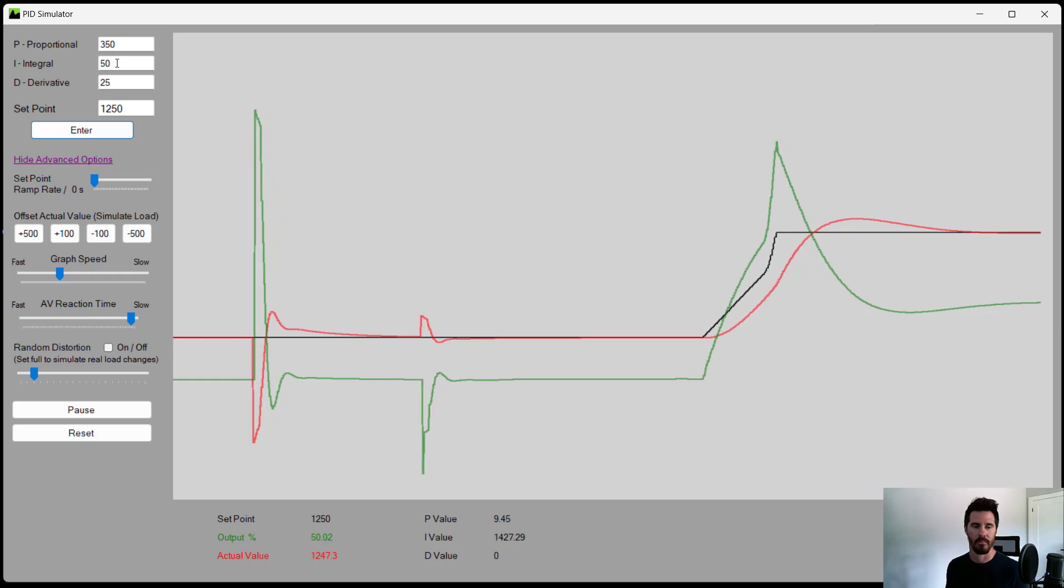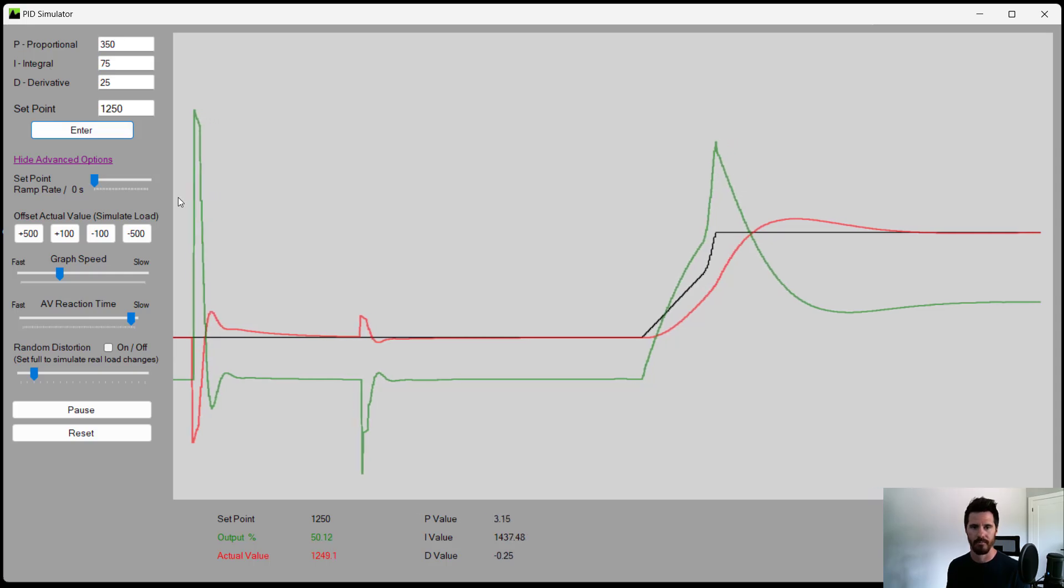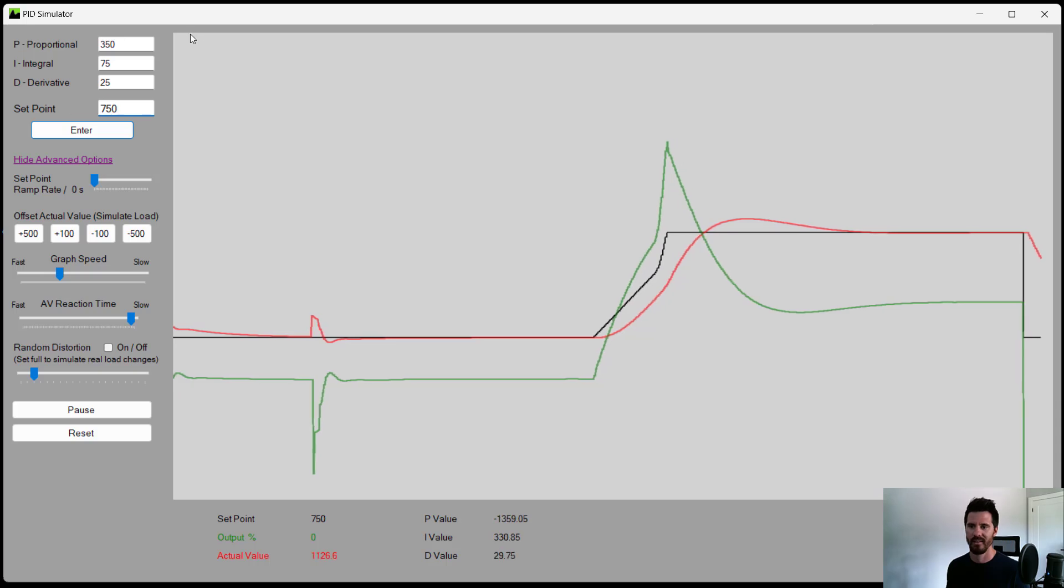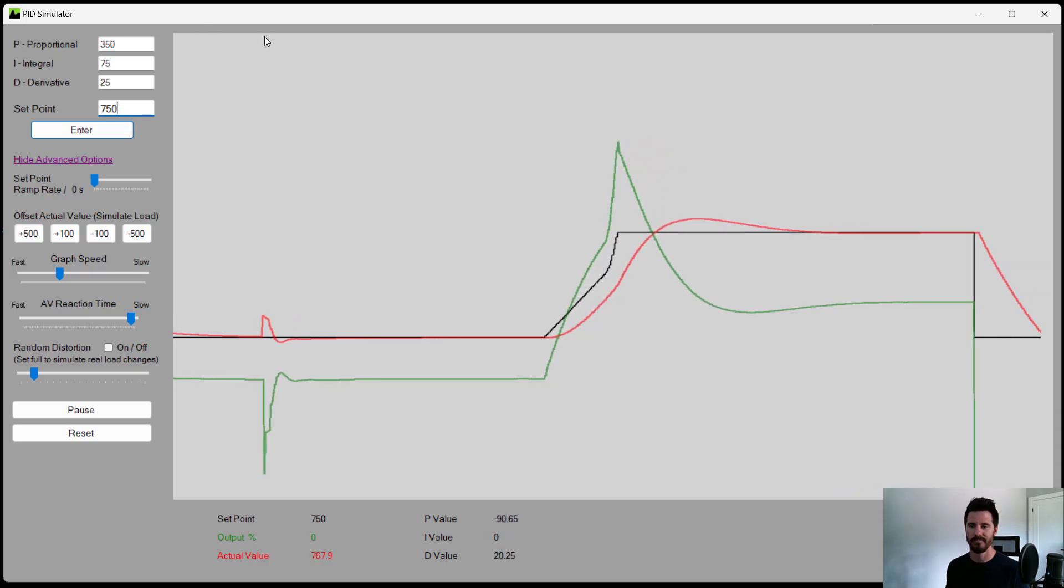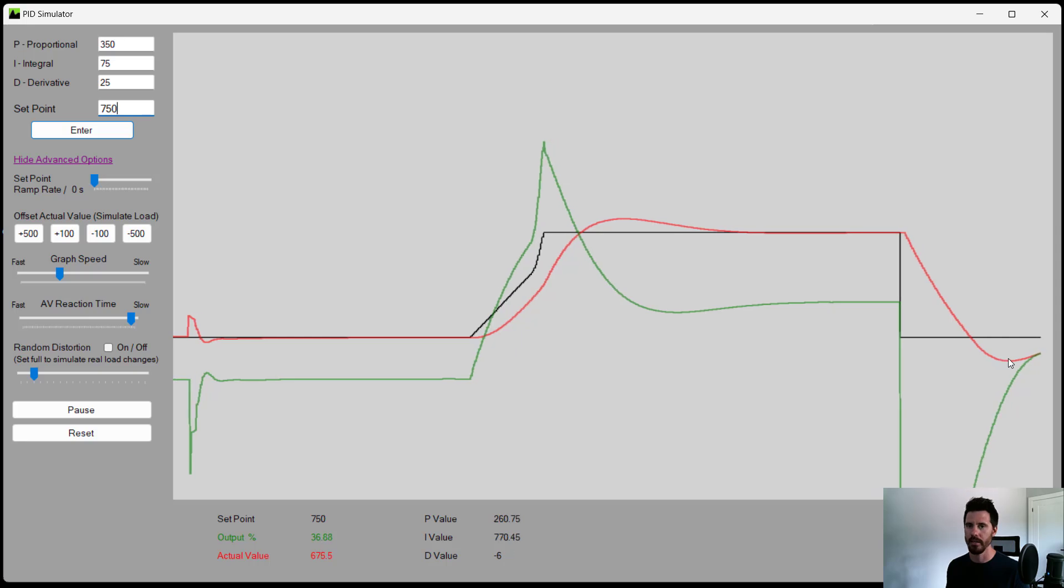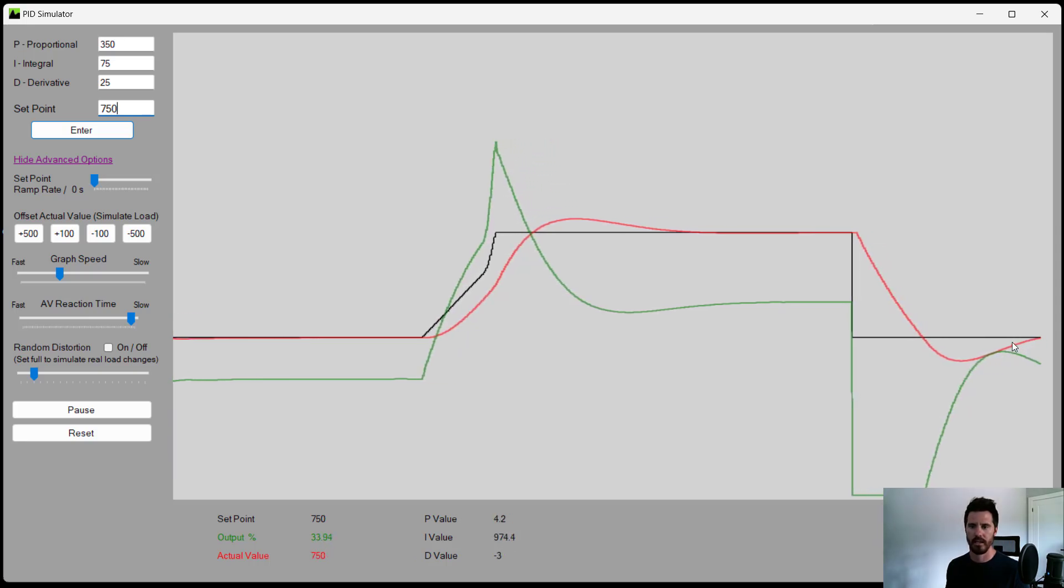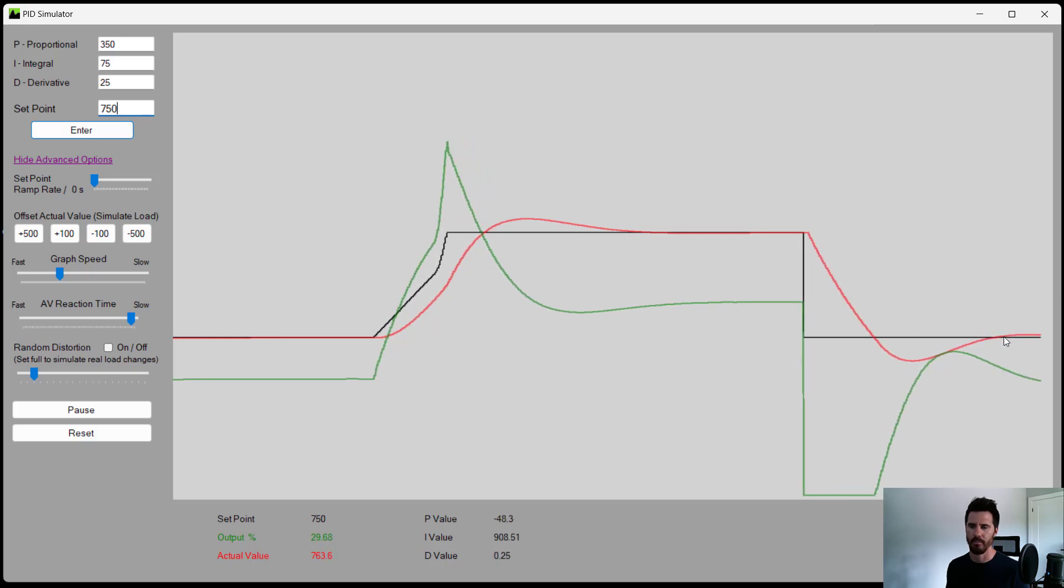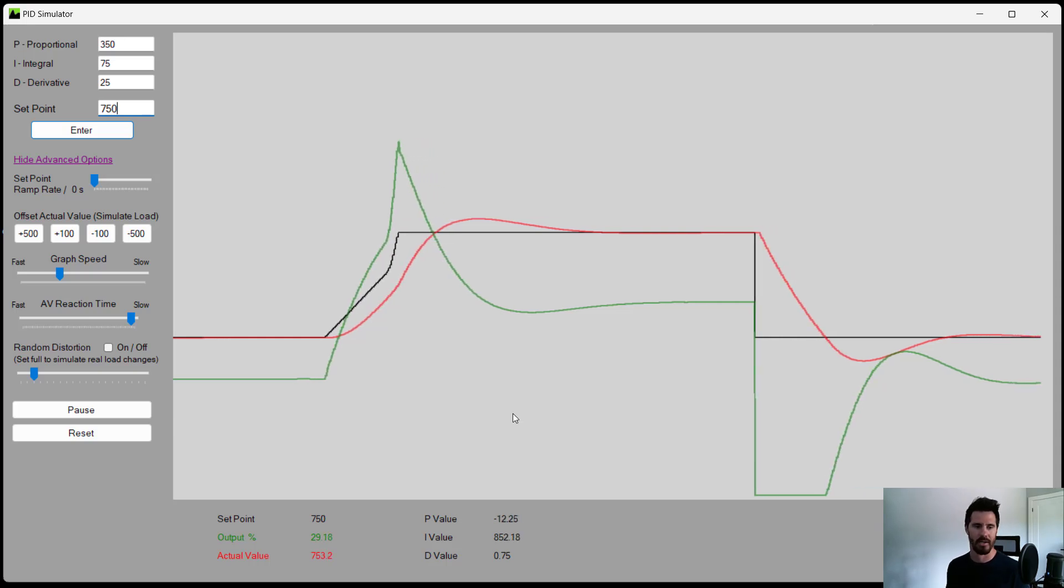With this software, now notice how it takes even longer for that temperature to come back and reach our set point. This is mimicking a temperature controller. So when I'm doing a temperature controller that's slow reacting, I might need a bit of a higher integral or I value. Let's try that again and see how it reacts to that one. Understanding this is a temperature loop, so it's never going to be immediate reaction.